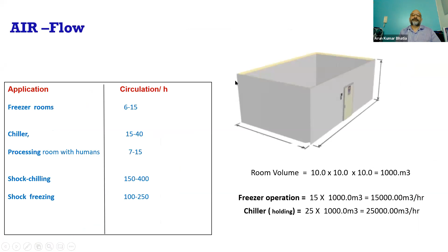Again, same way. If our refrigerant is ammonia, then we should have an evaporator selected for ammonia, based on system properties it is running on, temperature, air management, allowable pressure. For example, if we have a blast freezer, we may need external static pressure up to 200 Pascal, or 400 Pascal for special cases. There are other design factors which we can discuss in a different session on evaporator selections. Now the fan is an important component of these evaporators.